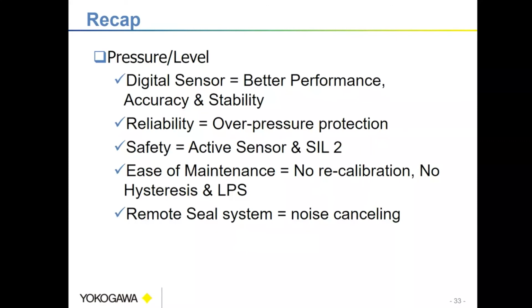So that's the advantage. And Charles, also, isn't the D capsule, because I have a lot of upstream oil and gas people, a couple of them are on here, the D capsule on the EJA, your 7200, I believe it's just 10 to 1. And like I said, it's specific to the different capsules. But that's also because if you're going that low, we would go with the C capsule. You know, it would cover all those ranges. We can cover any range you have. Basically, that's where we're going with that, and we can help with any application you've got is the main answer. But typically, a lot of them are 100 to 1 and 200 to 1. Just like Charles said, to reiterate, it's according to the actual transmitter, and we'll help you with that spec.